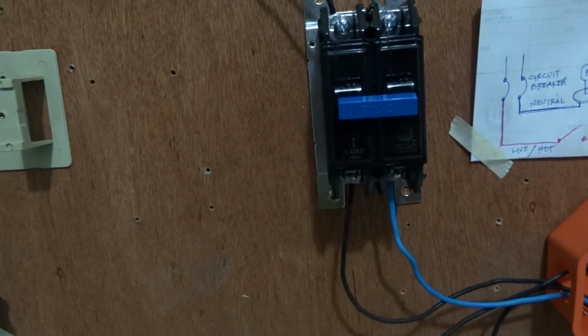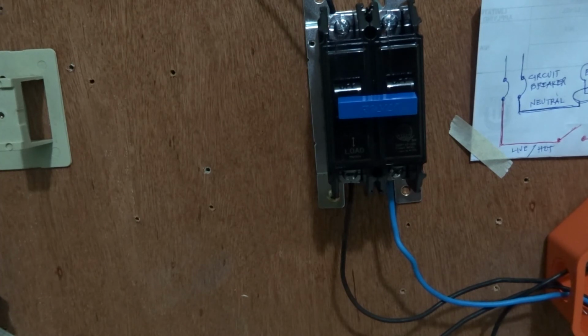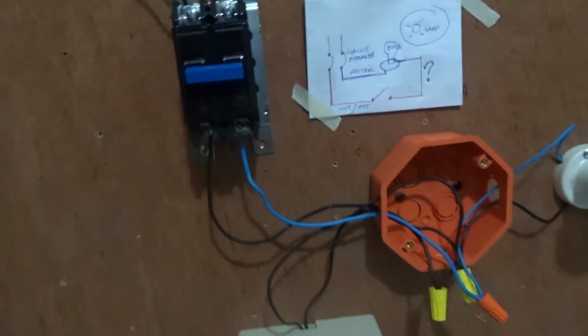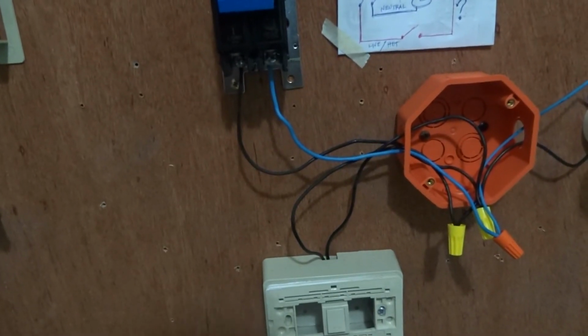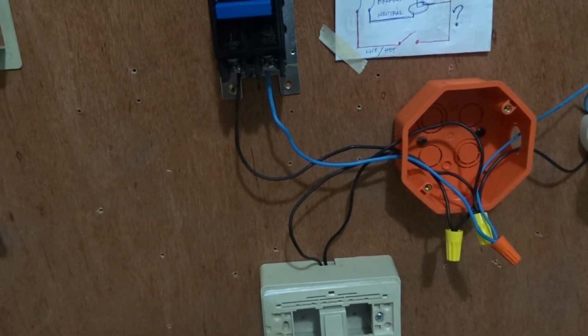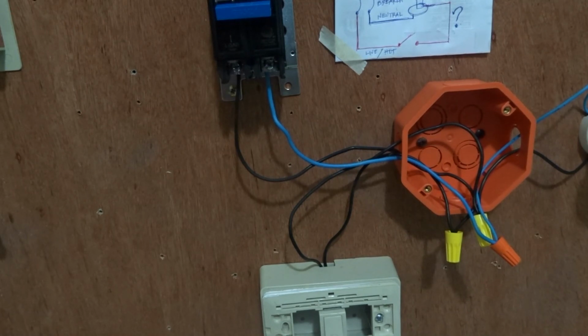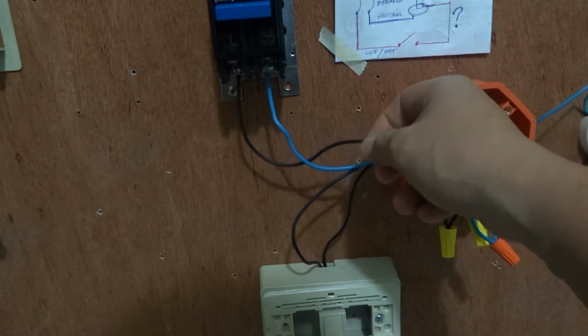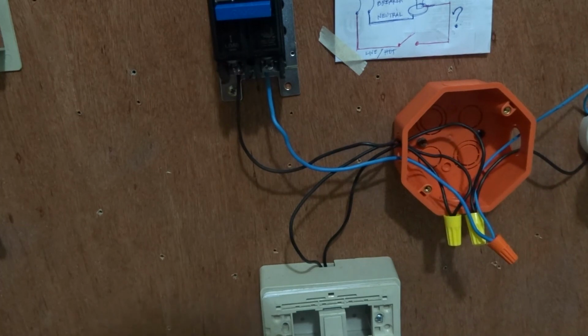In a short circuit or ground fault situation, a sudden reduction in resistance causes an uncontrollable amount of current to flow, and the circuit breaker responds to this by tripping. Example of a short circuit. You have to look for physical signs like burns or melted metal on wires, burning smells, or flickering lights. Once you have identified a potential short, use a multimeter with the setting of resistance or continuity.